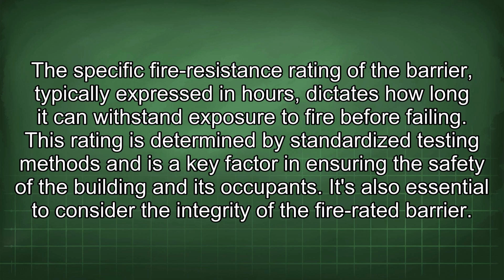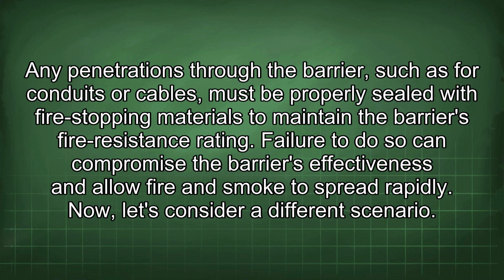It's also essential to consider the integrity of the fire-rated barrier. Any penetrations through the barrier, such as for conduits or cables, must be properly sealed with fire-stopping materials to maintain the barrier's fire resistance rating. Failure to do so can compromise the barrier's effectiveness and allow fire and smoke to spread rapidly.